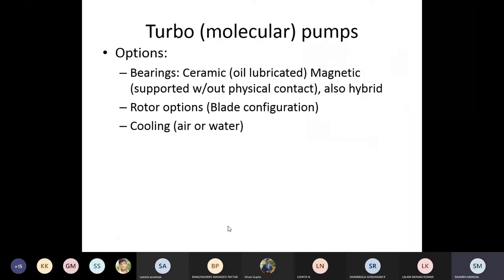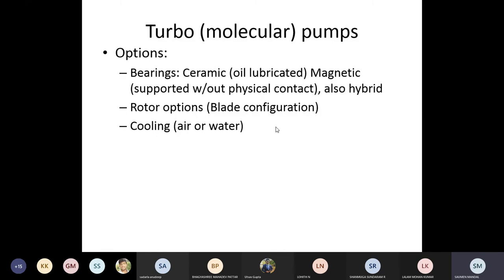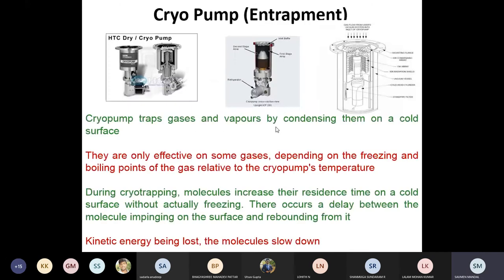The turbo molecular pump is versatile — it can generate vacuum from intermediate (10^-2 Pa) to ultra-high vacuum (10^-8 Pa). Since there is no oil, there is no oil contamination or burning risk. It is relatively faster than the diffusion pump. Cooling is also required due to heat generated by high-speed rotation. Components include ceramic or magnetic (or hybrid) bearings, angled rotor blades, and a cooling system.